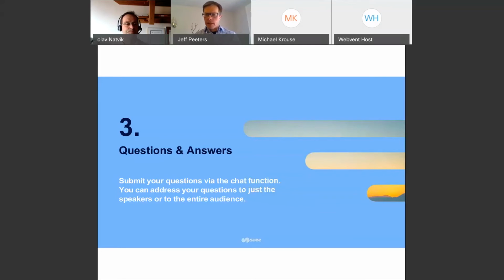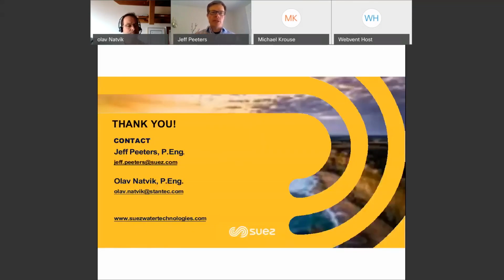And I think, time for one more question, which is quite interesting, one I'm passionate about, which is greenhouse gas emissions. So the ability of the technology to address greenhouse gas emissions comes from 2 places. First is the energy savings, of course. But the second one that's really interesting is the ability to reduce N2O emissions. So it's well understood that N2O is a powerful greenhouse gas, 300 times more powerful than CO2. And there's some evidence that suggests that N2O is produced as an intermediate in the nitrification and denitrification process. And MABR has some advantages to reduce that because of the special conditions in the biofilm, and mitigate it by collecting any N2O that's produced. So if that's something that you're interested in learning more about, you can follow up with me.